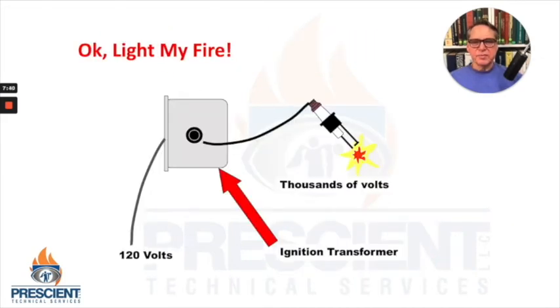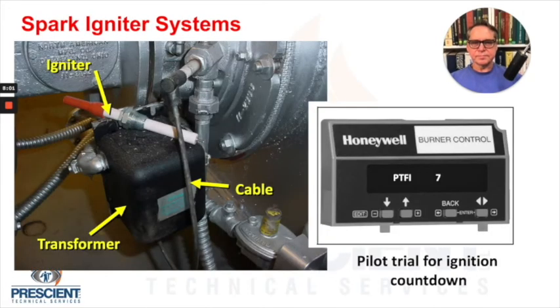So finally, once we've completed a purge and all the conditions have been met, we would send 120 volts to an ignition transformer. It would make 7,000 to 10,000 volts if it's a natural gas igniter typically, just kind of a little spark plug. And we would light a pilot or light a main flame if it's a direct ignited piece of equipment. Kind of in-depth on spark igniter systems. You can see on the left-hand side there in the picture, the ignition transformer, a cable, and then there's a ceramic igniter with a tip, the spark plug, if you will, and it's got a little crush sleeve around it.